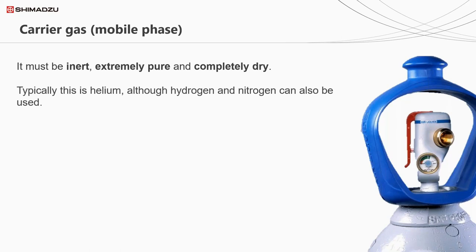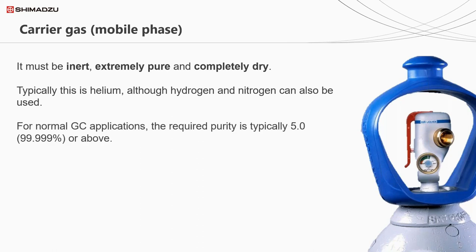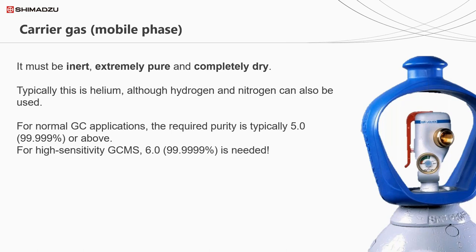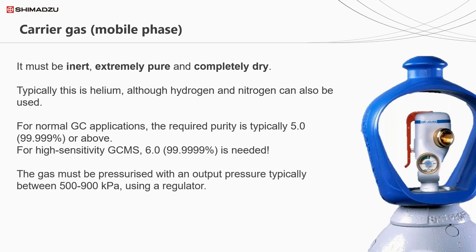Generally speaking, we use helium as a carrier gas for GC, although hydrogen and nitrogen are now more popular due to their availability and low cost. For your carrier gas, you do want it to be pure - typically we would say a purity of five nines, that's 99.999% or above. In some cases where you're doing very high sensitivity work or working with a GC mass spec, six nines is preferable. The gas must also be pressurized, so your gas cylinder will need to outlet the gas at somewhere between 500 and 900 kilopascals using a regulator.